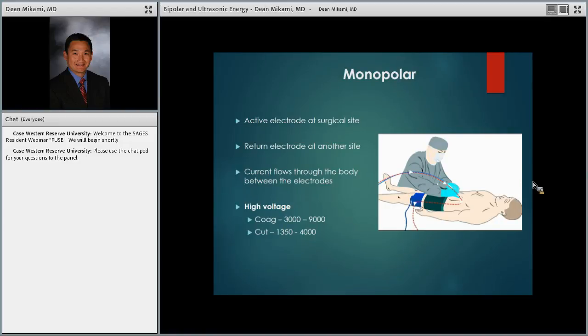So basically, current flows through the body between these two electrodes, and we use different settings, right? Amin talked about the multiple settings that we use on our ESU, and when we use coag mode, we use a very high voltage, 3,000 to 9,000 volts. In the cut mode, we use a much lower voltage, 1,350 to 4,000. So the take-home message in monopolar is we're trying to complete the circuit. You have your active electrode in your hand, and it is trying to complete the circuit by going to the return electrode.